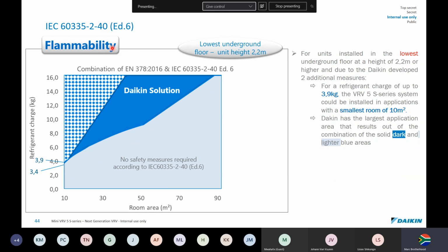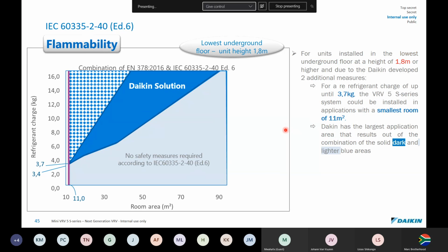So for units, still talking about flammability, for units installed in the lowest underground floor, so if you have a basement or whatever with a roof height of 2.2 meters or higher, and due to the Daikin development, there are 2 additional measures. For a refrigerant charge of up to 3.9 kilograms, the VRV5S system can be installed in applications with the smallest room still at 10 square meters. And Daikin has the largest application area, which is very similar to what I mentioned on the previous slide. This is also more about basements, so I'm going to skip this slide.